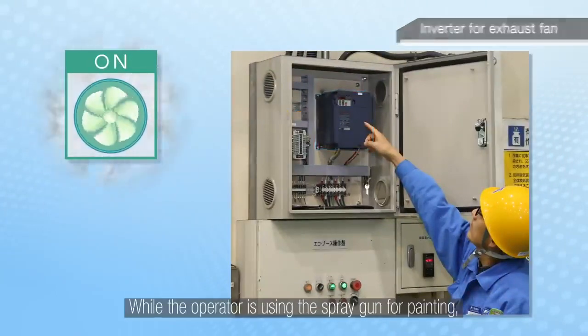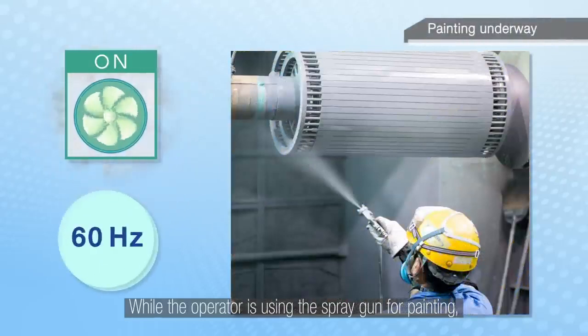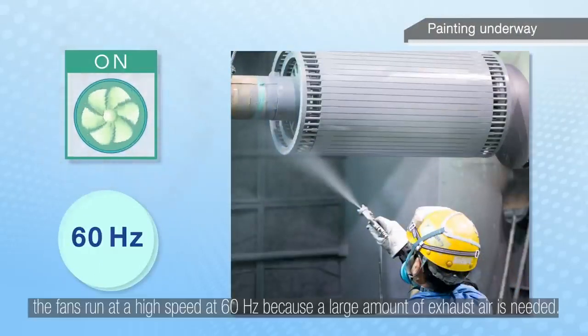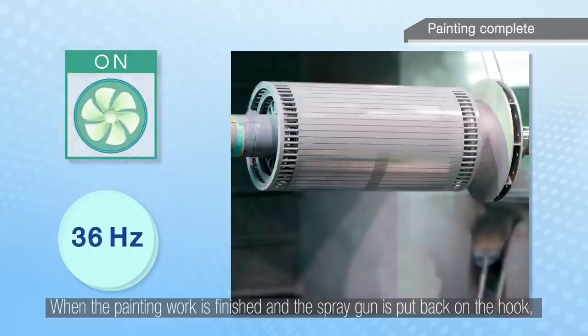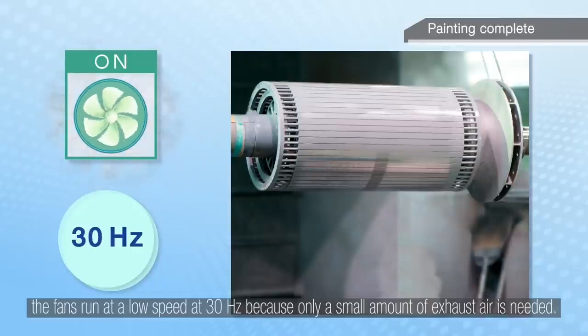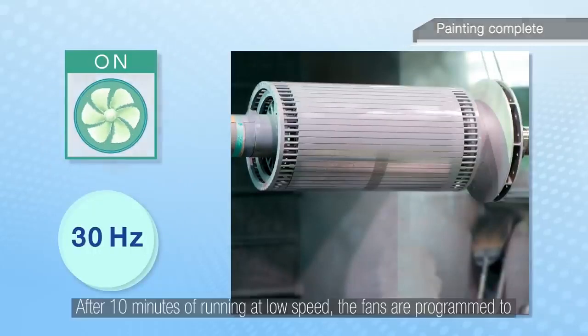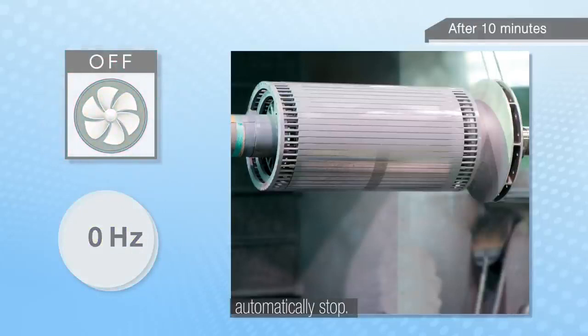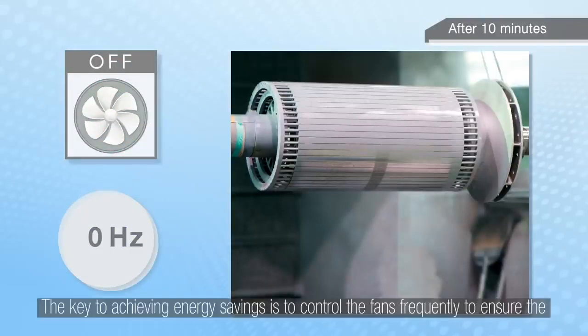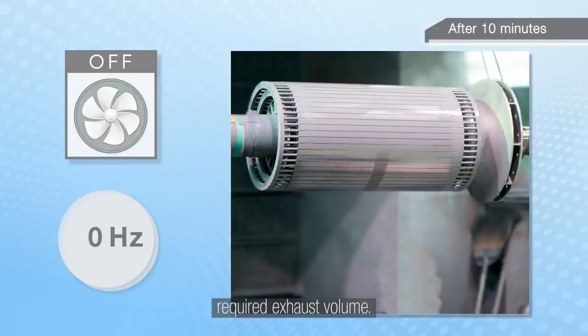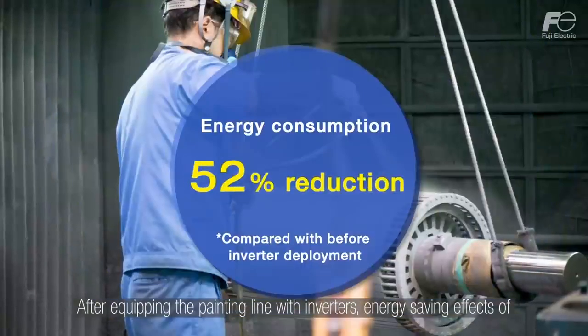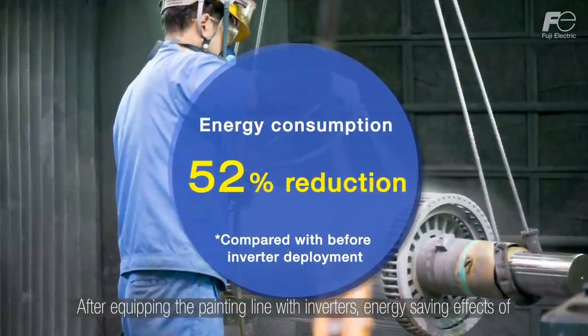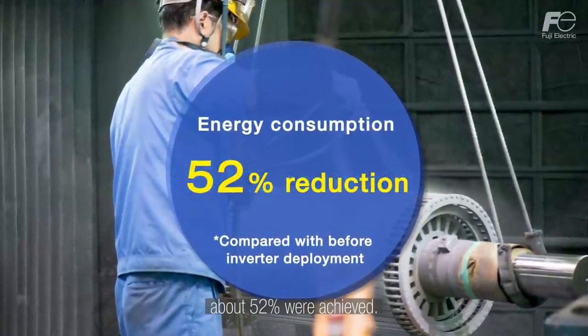While the operator is using the spray gun for painting, the fans run at a high speed at 60 Hz because a large amount of exhaust air is needed. When the painting work is finished and the spray gun is put back on the hook, the fans run at a low speed of 30 Hz because only a small amount of exhaust air is needed. After 10 minutes of running at low speed, the fans are programmed to automatically stop. The key to achieving energy savings is to control the fan's frequency to ensure the required exhaust volume. After equipping the painting line with inverters, energy-saving effects of about 52% were achieved.